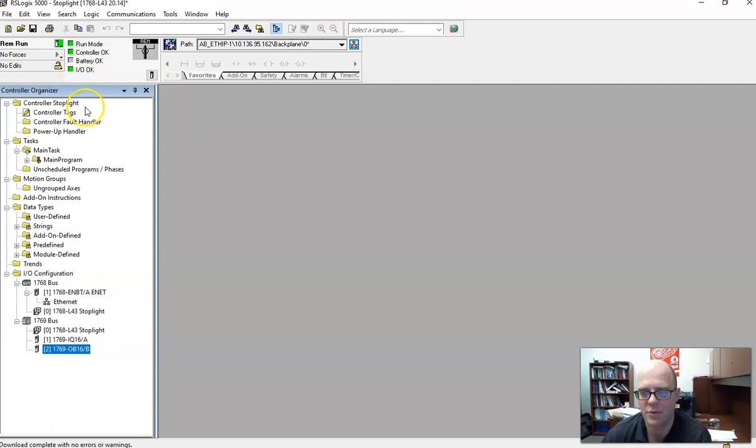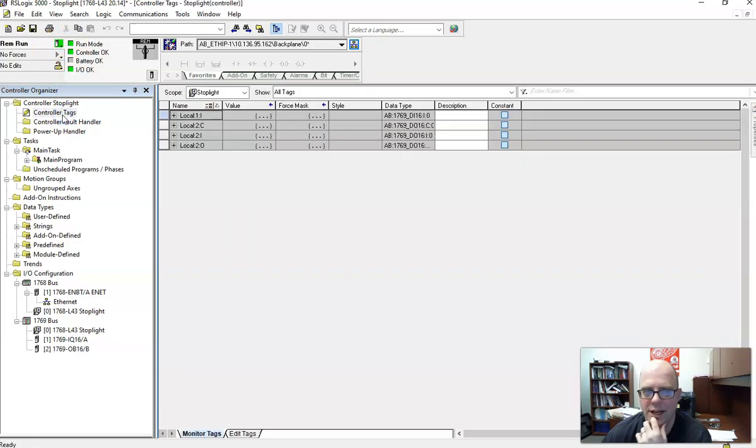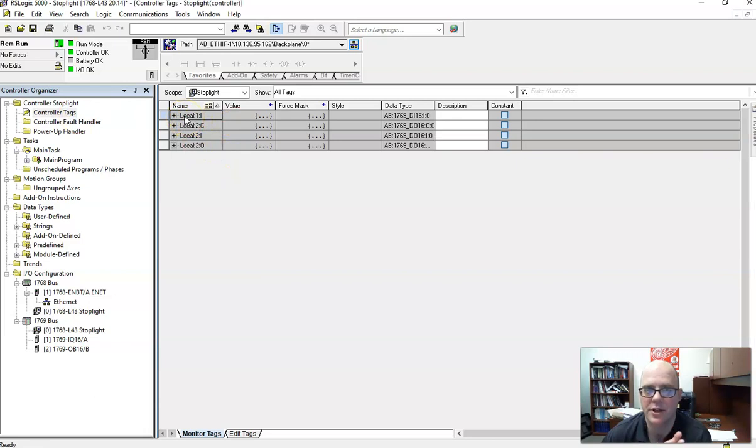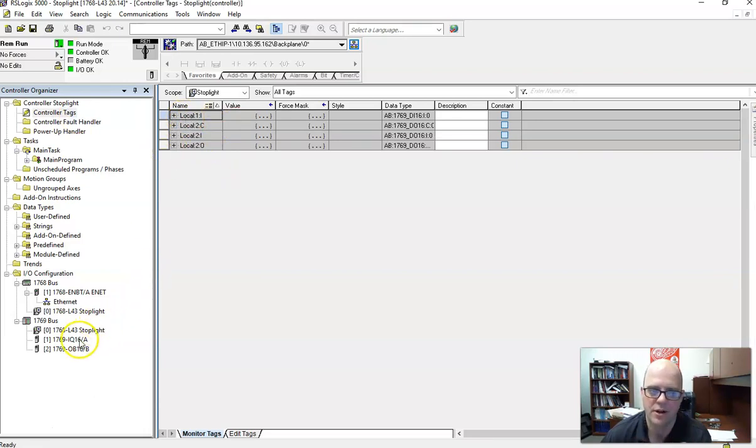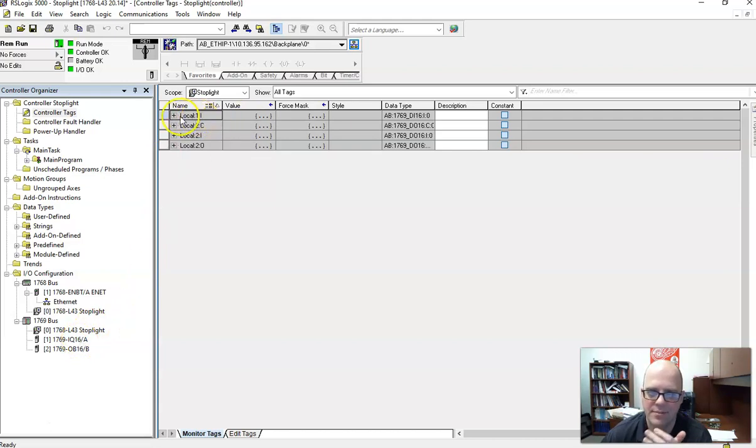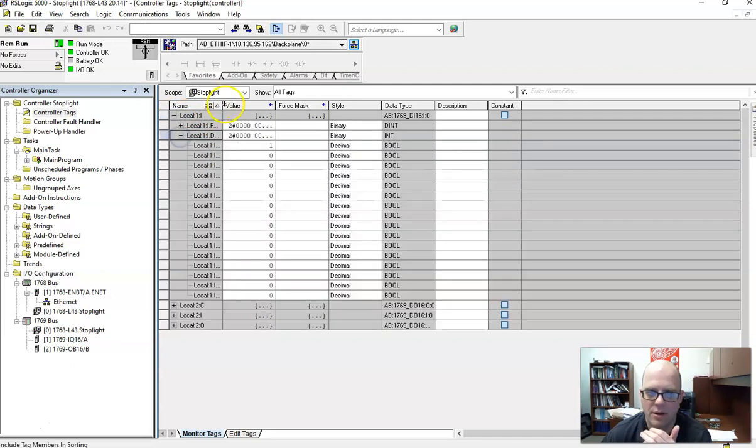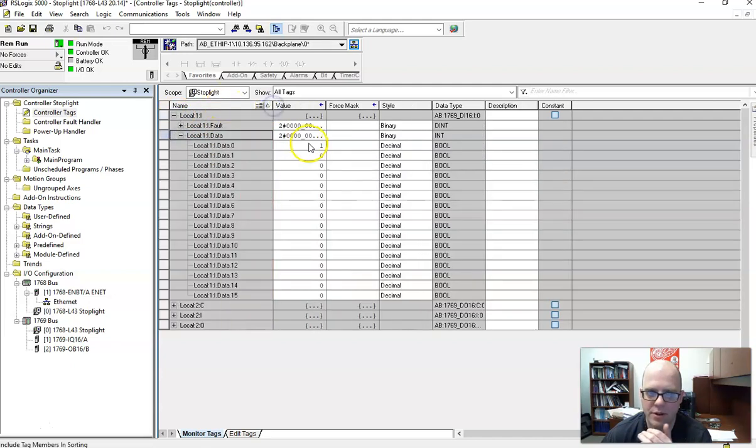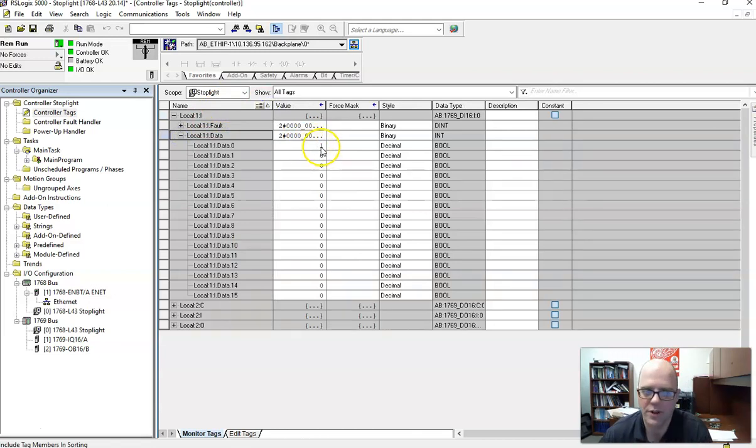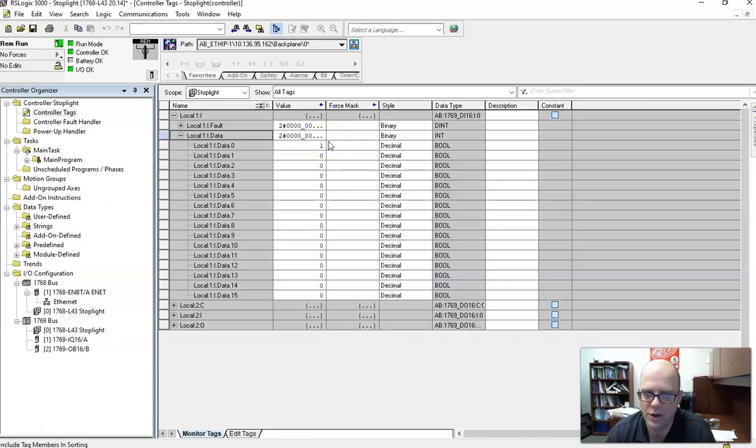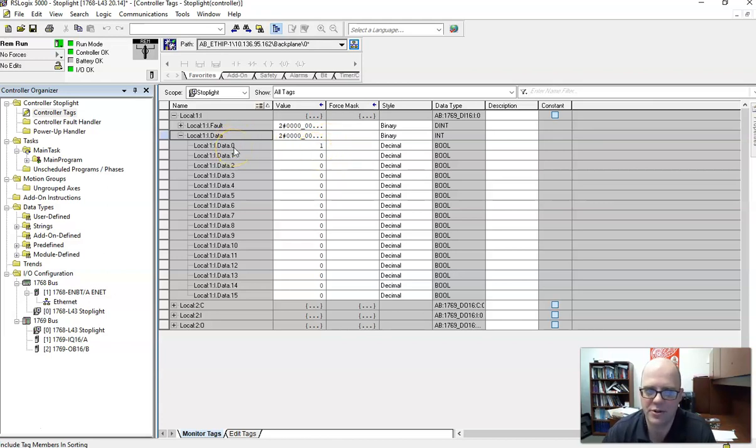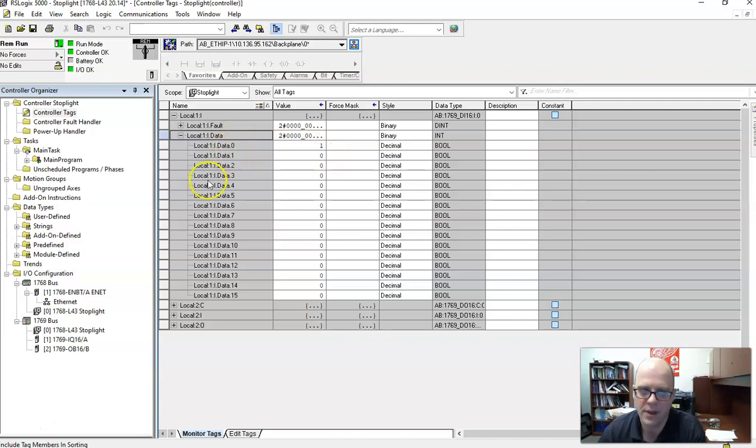And now what we're going to do is we're going to go into our controller tags. So I keep asking the question, how does it connect to the processor? Is it local? Yes. Our input cards are on slot one. So all of our inputs are going to be local, one, I, data, whatever the input is. And look, right now, you see a one there because there's input on in the back. So you can toggle that, and that should show up. And that should correspond to the zero screw that you tied into.